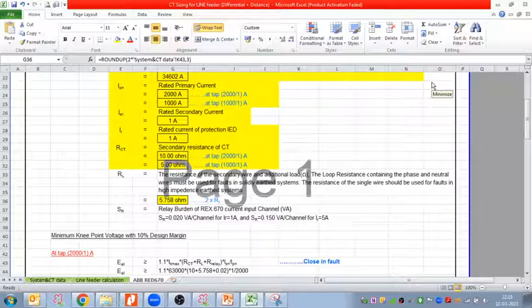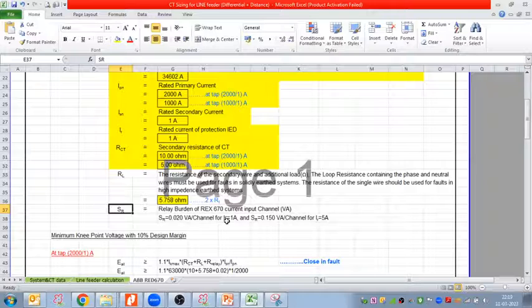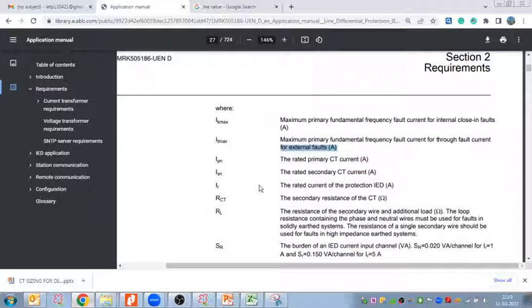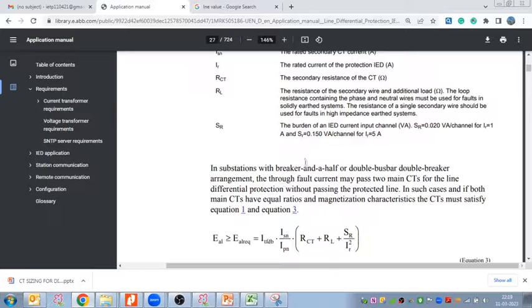Yeah, yeah, lead resistance, correct. Congrats. So what cable, what size of the cable we are using, and what is the length of the cable, based on that we calculate the lead resistance, right? SR is the relay burden. I hope that you can get it from the application manual. So if you see here, SR was not discussed, so you need to take SR from your relay application manual.